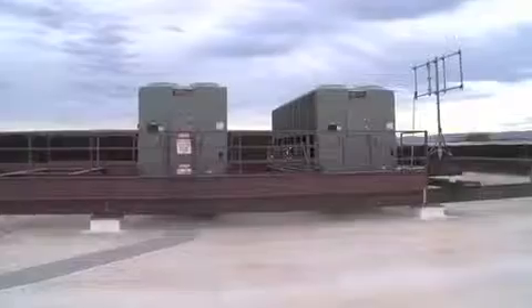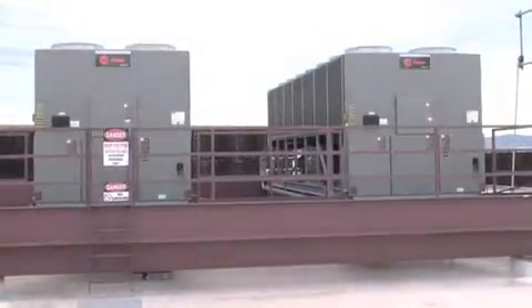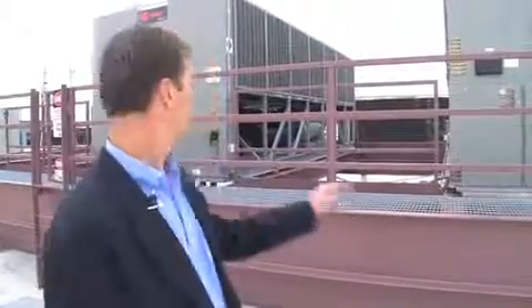These are our chillers. These are dedicated to the facility. Everything we do with the data center, we do with N+1 redundancy. If one chiller were to fail for some reason, we always have a backup one. As we expand the data center and need more cooling capacity, we will just continue to add these in pairs.